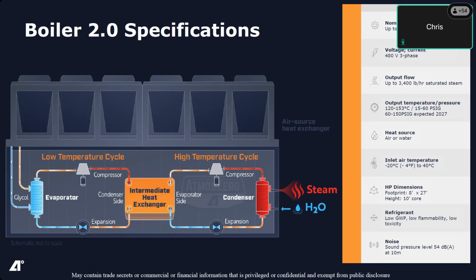In the case of a water sourced unit, that air coil goes away. You put a tiny little plate and frame heat exchanger pretty much where that first cell is on the left, and you can tie in any kind of process water or waste heat that you may have. A lot of projects look at using cooling towers, look at using the condenser returns off chillers, or sometimes process cooling directly. And we can achieve higher COPs, but it typically takes a little bit more integration on the customer side. You can see some specs there.